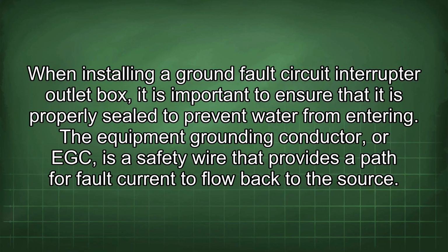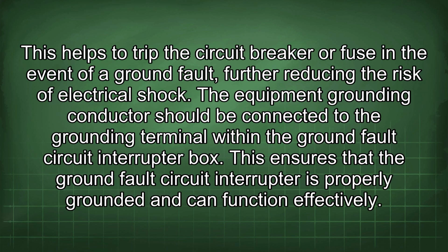When installing a ground fault circuit interrupter outlet box, it is important to ensure that it is properly sealed to prevent water from entering. The equipment grounding conductor, or EGC, is a safety wire that provides a path for fault current to flow back to the source. This helps to trip the circuit breaker or fuse in the event of a ground fault, further reducing the risk of electrical shock. The equipment grounding conductor should be connected to the grounding terminal within the ground fault circuit interrupter box. This ensures that the ground fault circuit interrupter is properly grounded and can function effectively.